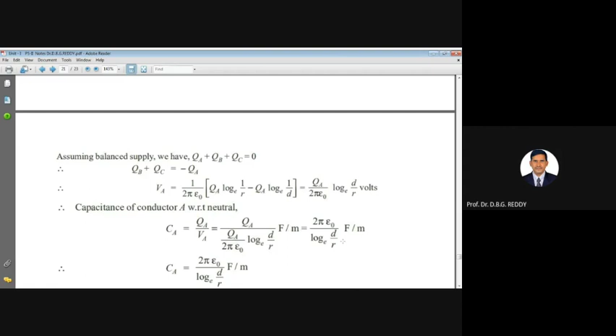Now asymmetrical spacing means the conductors may not be at equal distances: D1 is not equal to D2, D2 is not equal to D3. Here also we will get the same expression. Wherever D was there, the cube root of D1 D2 D3 will be used. Now CA is equal to Q by VA, that is 2 pi epsilon naught by log e base of that. Remaining all are the same, only the D value will change, between symmetrical and asymmetrical spacing. Since D1, D2, D3 are not equal, take the cube root of the product of D1, D2, D3 and apply the value, and you will get the capacitance from the conductor to neutral.